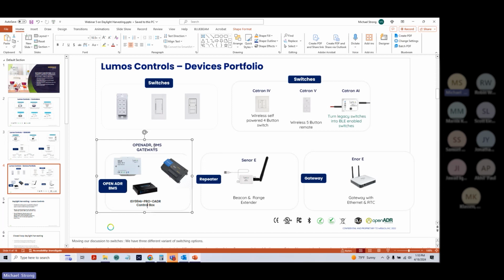But in reality, the restaurant owners, building owners, they will get stipends from the utility companies to allow them to utilize the Open ADR gateway. Our BMS gateway, one of the exciting changes that is probably coming along, and I say probably because I don't want to get too far ahead of ourselves, but we may be able to drop the second gateway relatively shortly. Right now, as it stands, we use our Iris E to talk to the ENOR E, and this Iris E then talks to our Niagara box. It's our Jace 8000, I believe. Just off the top of my head, it's Jace 8000.